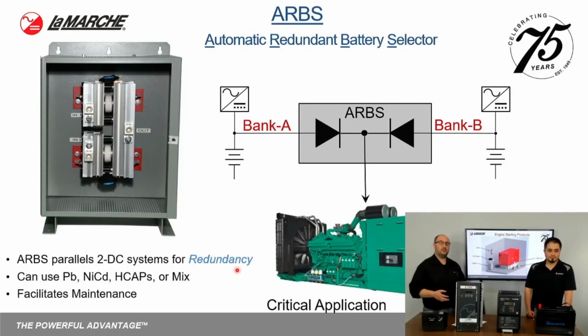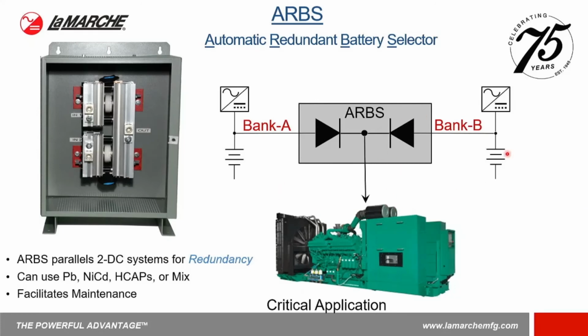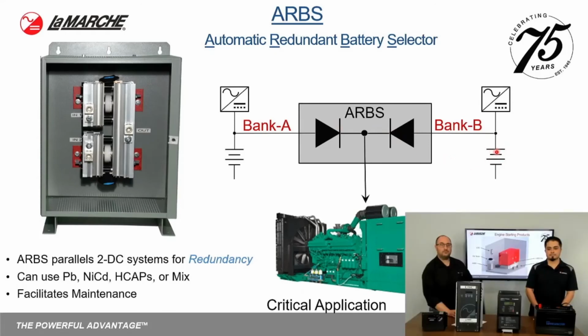Now, on smaller generators, you're not going to be able to necessarily fit two separate DC systems, but in a larger and more important and more critical application, an ARBS certainly allows you the redundancy of having as many batteries on each bank and as large of a charger on each bank as necessary. What's great about this is because of the blocking diodes, it allows you to facilitate maintenance on the batteries. So for a very highly critical application, I would definitely recommend using an ARBS.